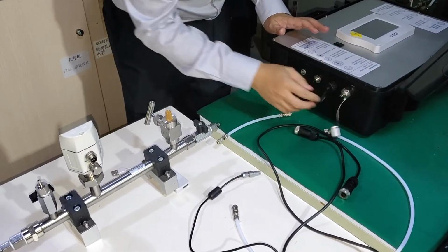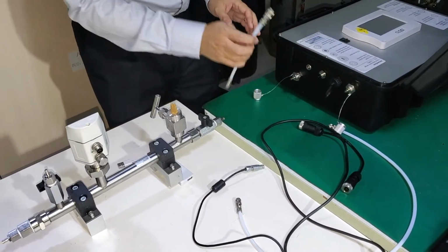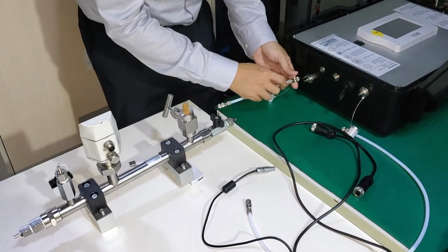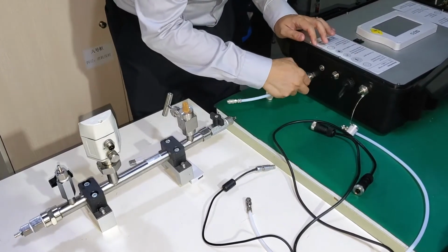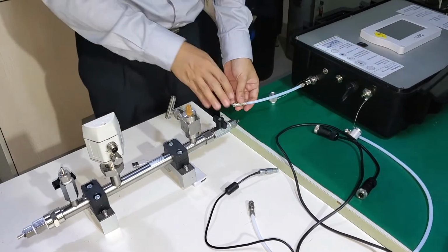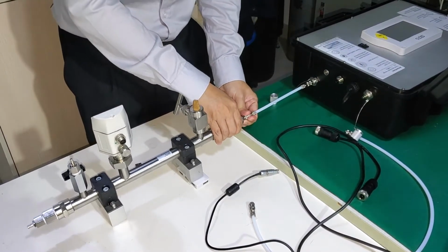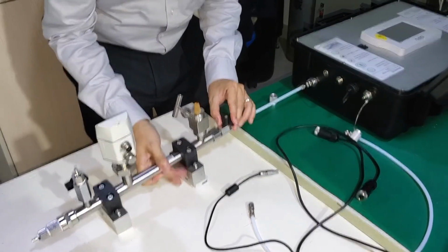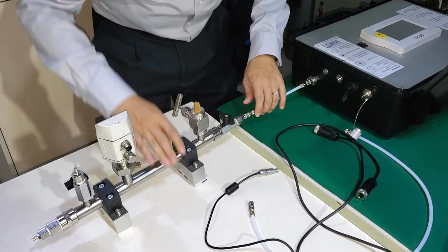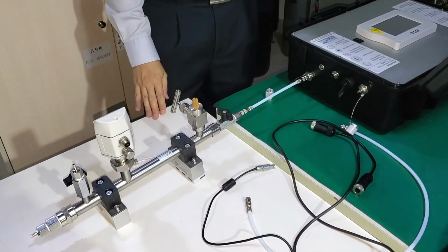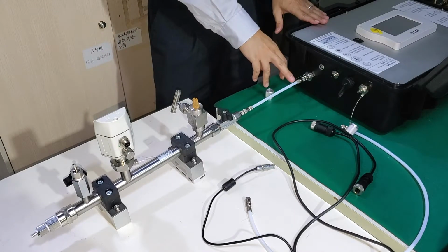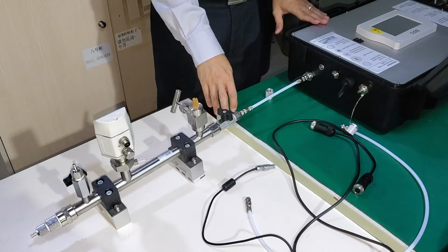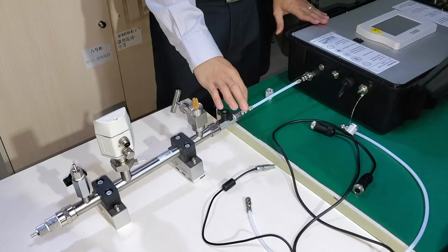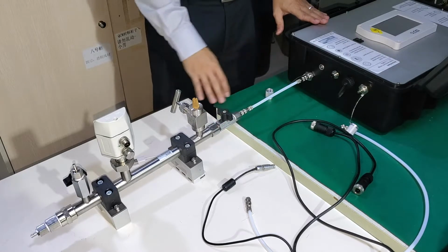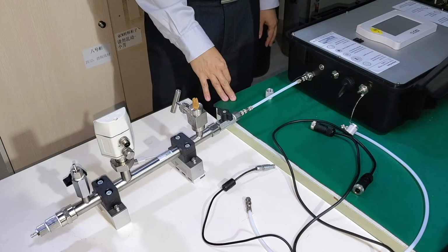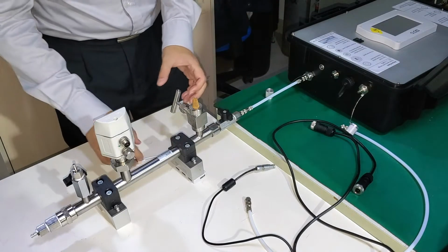First of all, we need to unplug the cap, okay, and then you connect the Teflon hose. This one is actually for the air particle measure. As you can see, the Teflon hose can gather the air particle sample from the center of the tube, so it will comply with the ISO 8573 standard. Let's continue, okay?